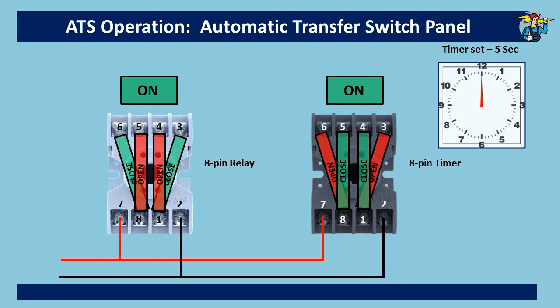The relay and timer got power — the OFF position changed to ON. On the relay, the normally closed positions are now open and the normally open positions have changed to closed. On the timer, however, the changes do not appear yet. With power ON, the clock starts counting, and as soon as it reaches the set time of five seconds, the changes happen. This delay ensures changeover does not occur until the restored power is stabilized — it is a safety precaution.